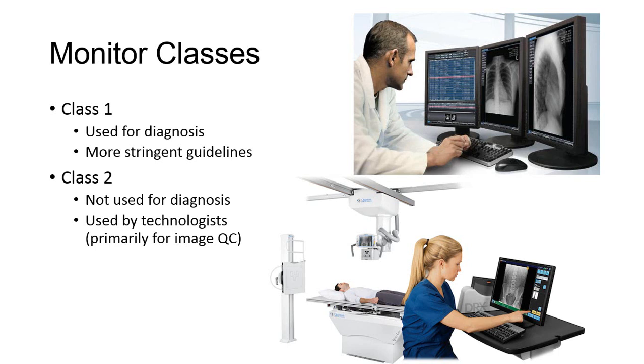A SMPTE test would traditionally be performed upon installation of the monitor after baseline adjustments are set. Then periodic SMPTE testing would be performed to compare to baseline results. Let's take a look at the types of quality control testing that's typically performed on display systems in a radiology department.